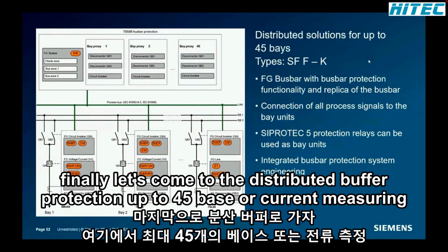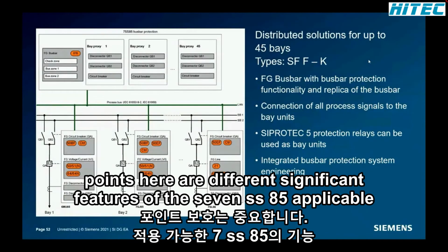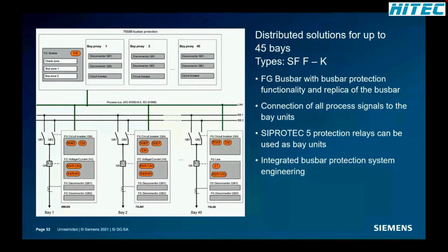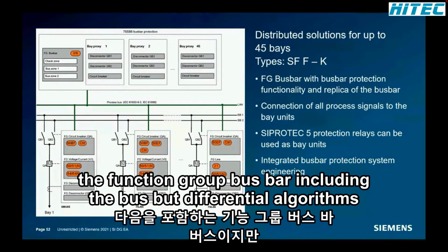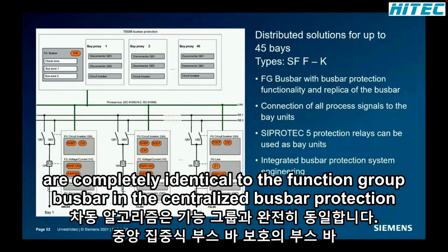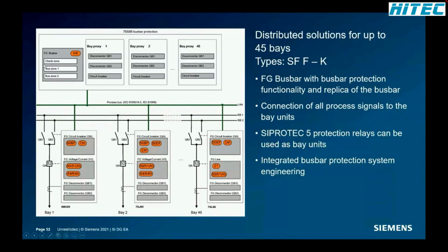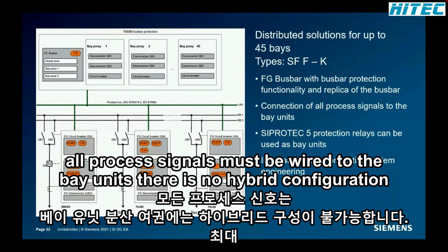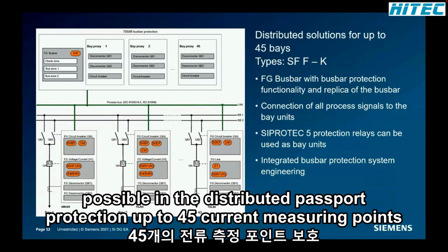Finally, let's come to the distributed busbar protection up to 45 bays or current measuring points. Here are different significant features of the 7SS85 applicable. The function group busbar, including the busbar differential algorithms, are completely identical to the function group busbar in the centralized busbar protection. All process signals must be wired to the bay units. There is no hybrid configuration possible in the distributed busbar protection up to 45 current measuring points.